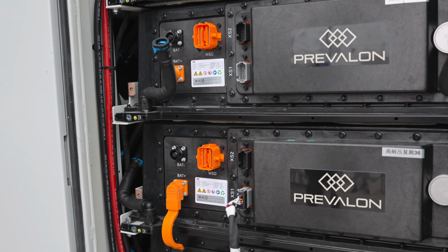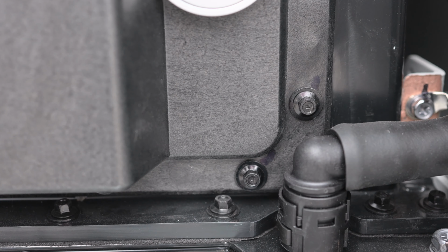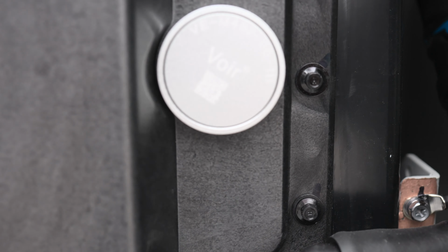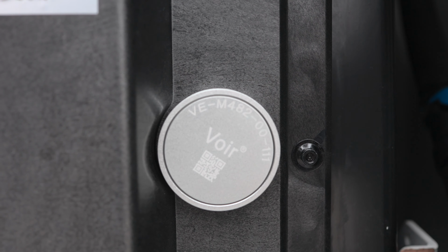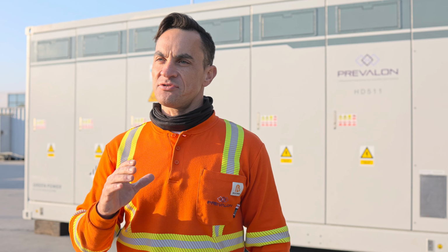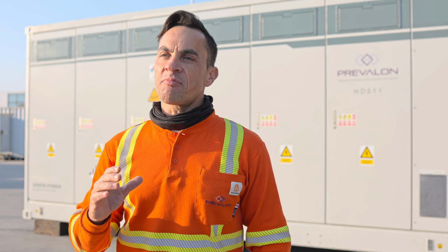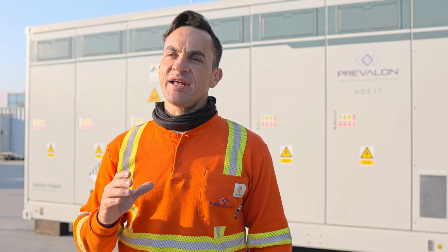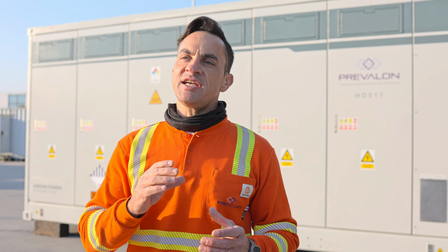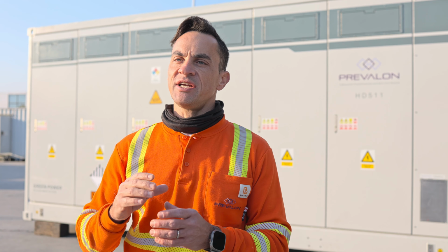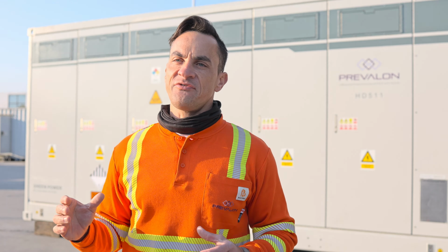a side-to-side, back-to-back configuration. Heat transfer is mitigated by employing fire-retardant heat-absorbing material between cells and modules. In addition, the battery compartment is wrapped in an EI60 rated insulation material, reducing heat transfer from enclosure to enclosure in the event of a catastrophic failure event.